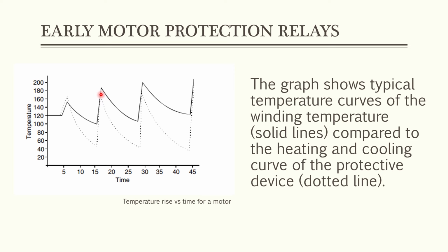Ganito nakainit yung protective device natin without knowing na winding temperature natin is above na pala doon sa protective device natin. So, dito sa first 5 to 10 seconds natin, pwedeng mag-trip na yung protective device without exceeding the winding temperature limits, kahit hindi pa niya naabot yung limit niya, nagtitrip na. Dito naman sa second peak, hindi pa nag-trip yung protective device natin pero umabot na or nag-exceed na doon sa limit ng temperature ang winding temperature natin. So, there's a little discrepancy when we compare the winding temperature to the protective device temperature of early motor protection relays.